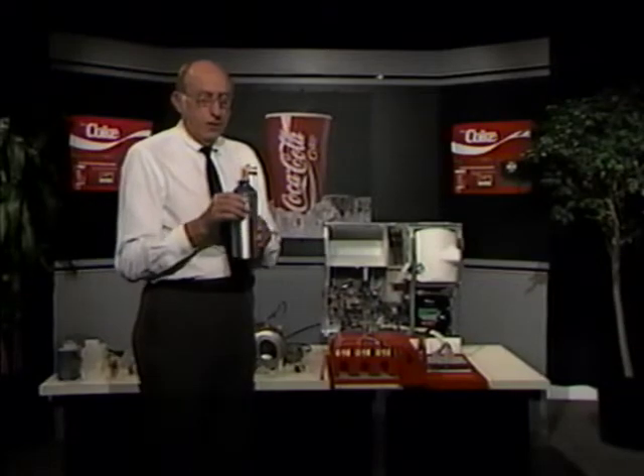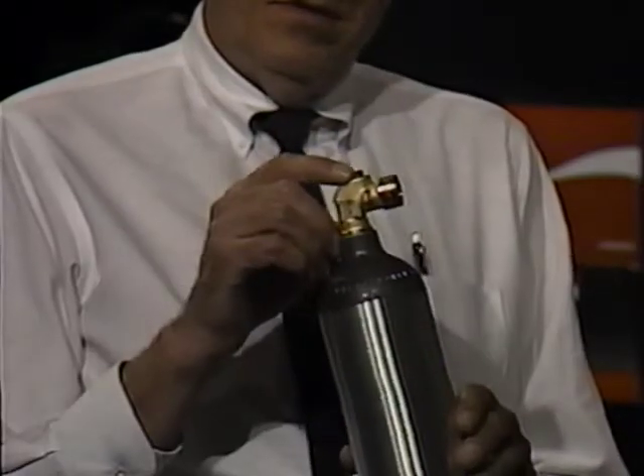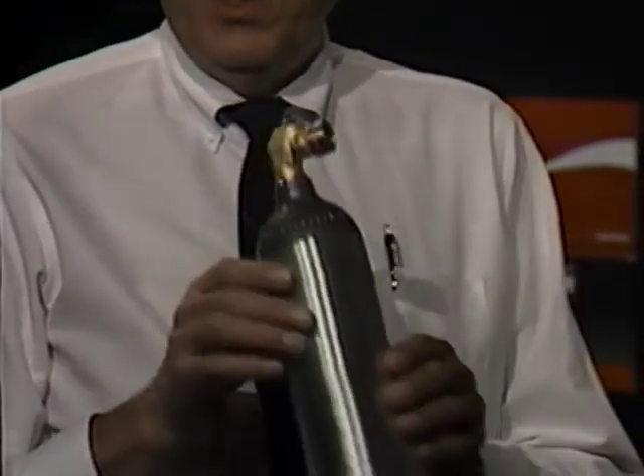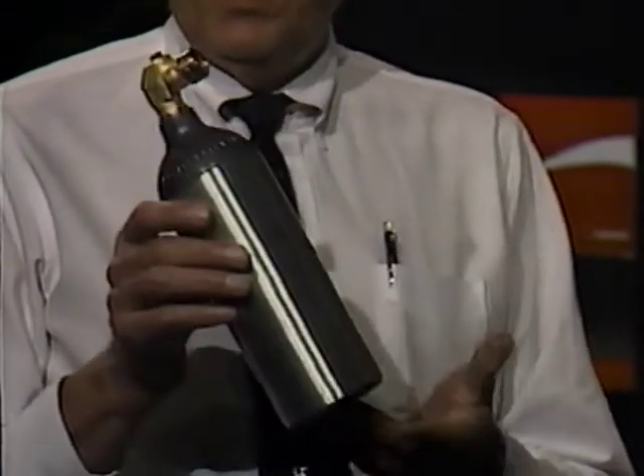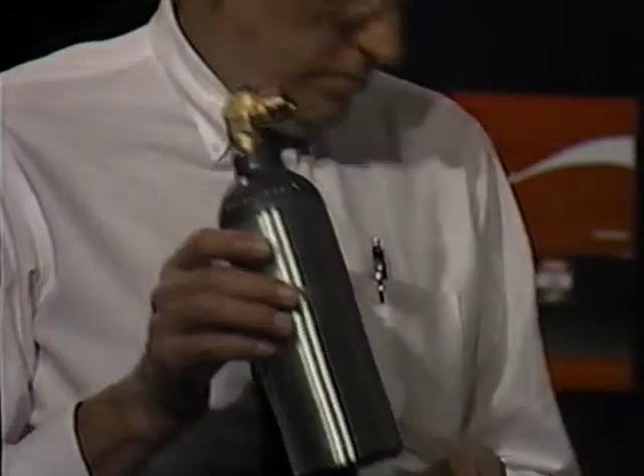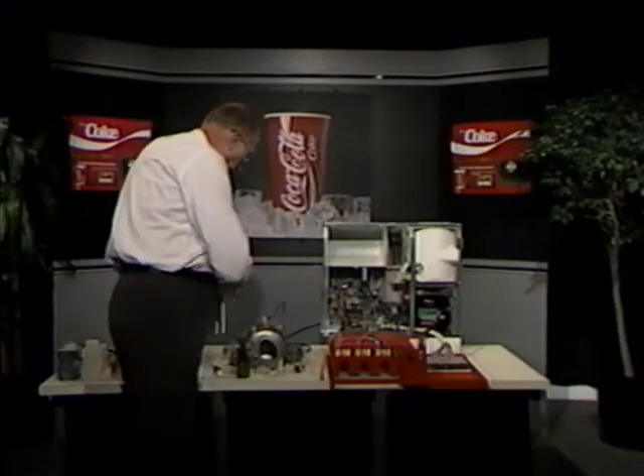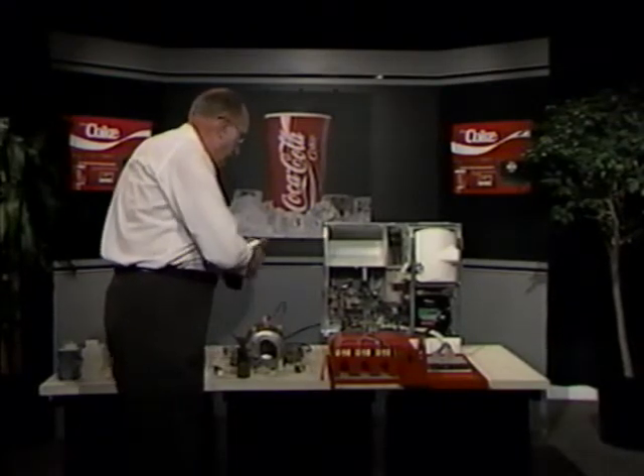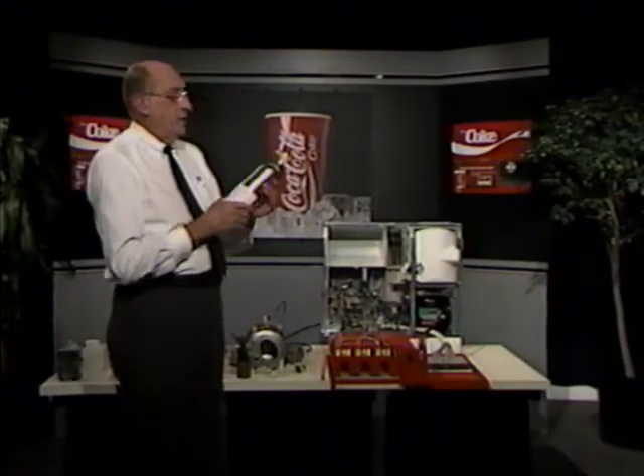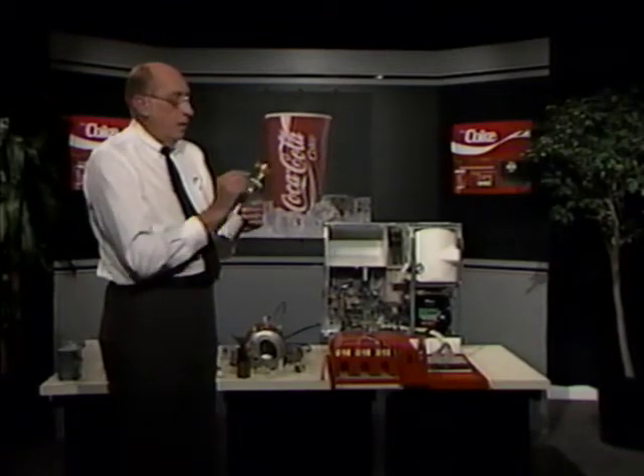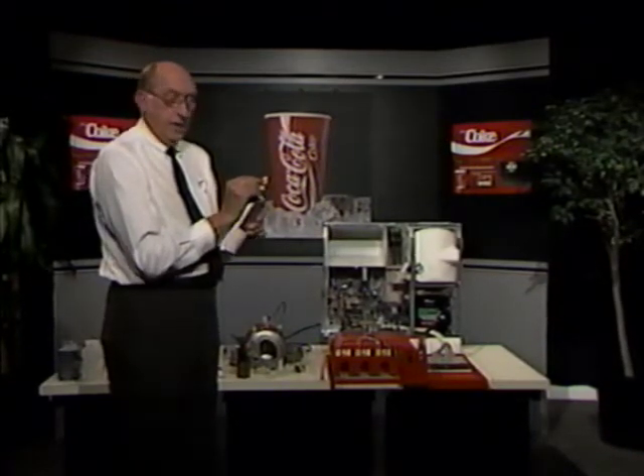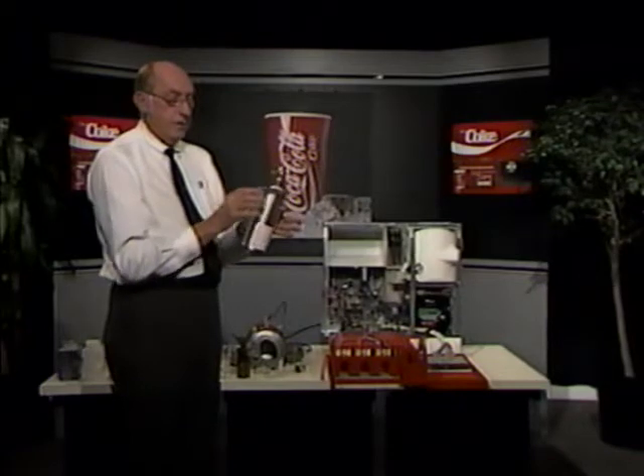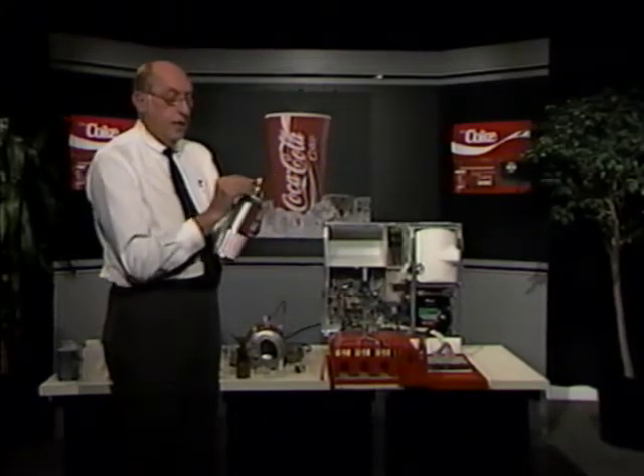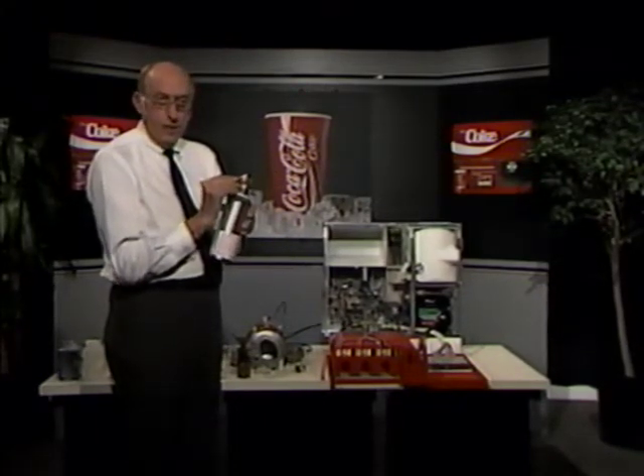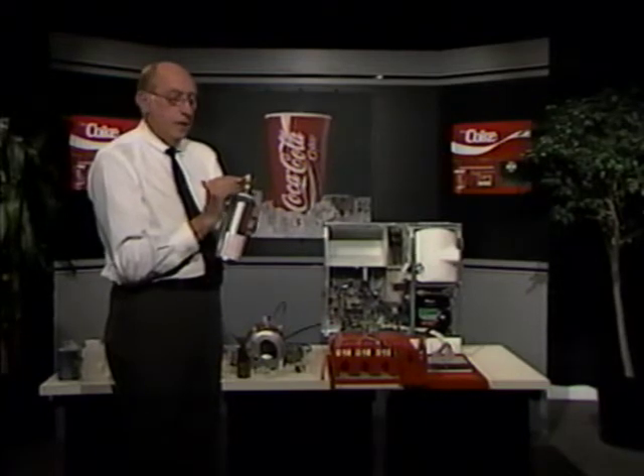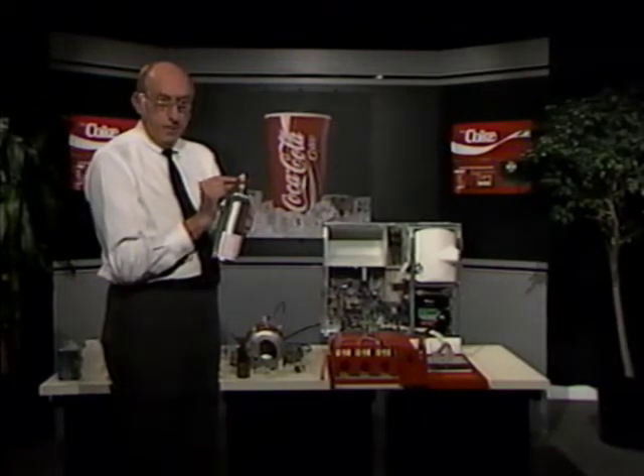The CO2 cylinder is equipped with a safety burst disc which relieves the pressure in case of overfilling or in case it's subjected to high temperatures. We can tell whether a cylinder is full or empty by pressing on this little pin. If you have any occasion to wonder whether you've got CO2 in a cylinder or not, you can tell whether it's empty. If the pin presses in easily, then you know that the cylinder is empty.